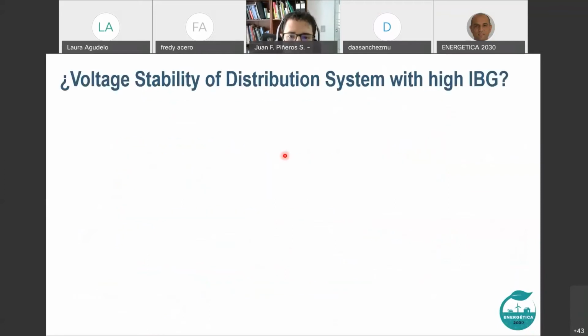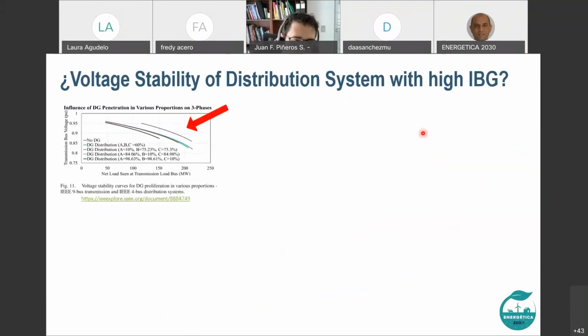Another point is what will happen with the voltage stability in the distribution system when we have high penetration of inverter-based generation. Some papers are worried about this, because when you increase the level of inverter-based generation, in general distributed generation of this kind, you can have problems with voltage stability. Why? Because remember, in general, they don't provide reactive power. Then if you depend only on that, and you have events, you can have problems.